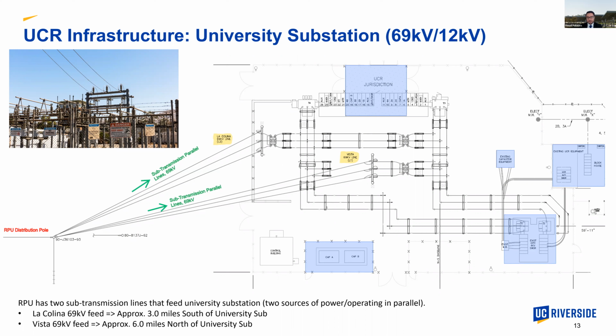The way it's configured, we have 69,000 volts, which in a power system is considered a sub-transmission line coming into the substation, then transformed via a transformer down to a 12,000 volt system to feed into our buildings. There's a little redundancy built into this setup between the city and the substation. For example, if one set of lines goes down, we're still able to power the campus at an adequate level, depending on the time of year, since hotter or cooler weather plays a factor in power demand. If one of these lines does go down, the campus will feel some sort of momentary blip in the system, which we've actually experienced before.